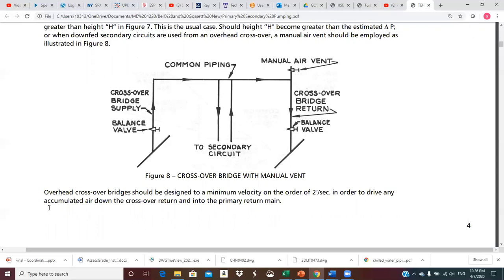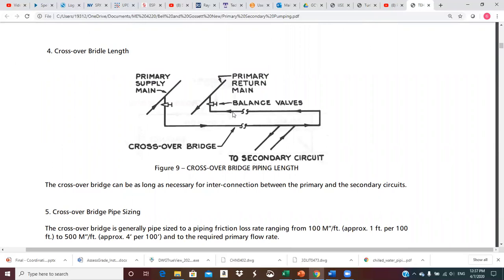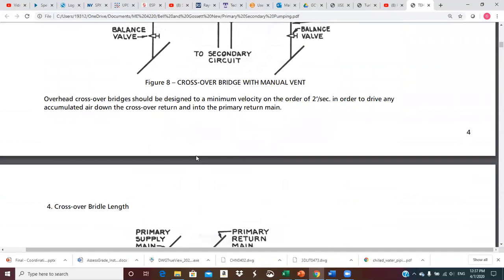Overhead crossover bridges should be designed to a minimum velocity on the order of two feet per second in order to drive any accumulated air down the crossover return and into the primary return main. With enough velocity, we can drive the air down into the return main where it goes back to the air separator. The crossover bridge can be as long as necessary for interconnection between primary and secondary circuits — it doesn't have to be a symmetrical shape.